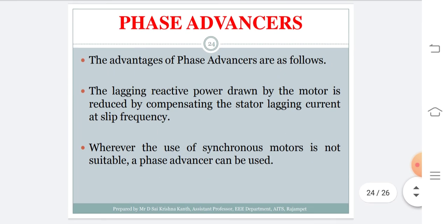Coming to the advantages of phase advancers: the lagging reactive power drawn by the motor is reduced by compensating the stator lagging current at slip frequency. Wherever the use of synchronous motors is not suitable, a phase advancer can be employed.